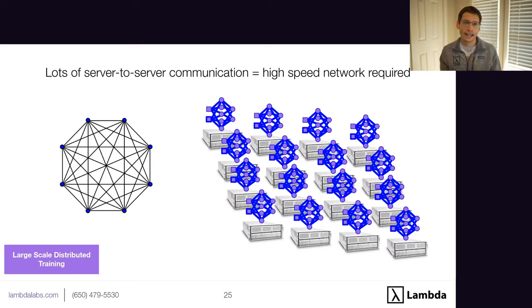For data center floor planning, talk to your co-location provider and ask: what racks are you providing, how much power is available per rack, what's the maximum density allowed, and how high in kilowatts can a rack go based on HVAC capabilities? Pull that floor plan into CAD software to measure cable lengths and cable runs. It's critical to ensure you're not busting the power budget provided by your data center.